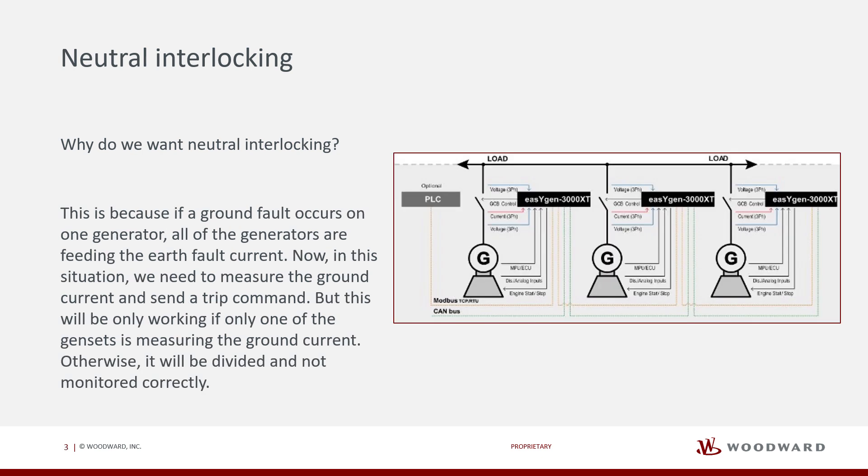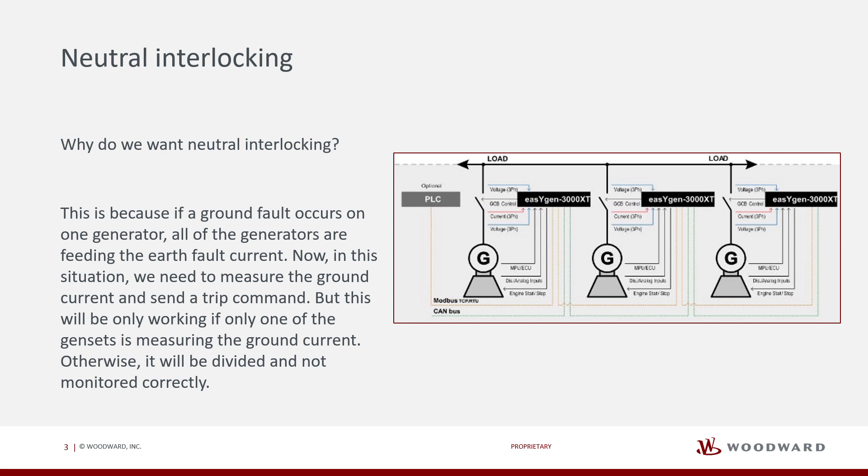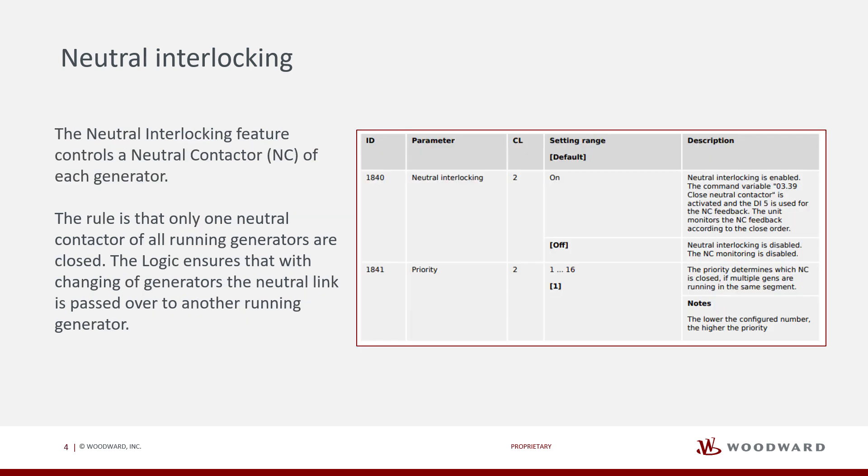This is because if a ground fault occurs on one generator, all of the generators are feeding the earth fault current. Now, in this situation, we need to measure the ground current and send a trip command. But this will only be working if only one of the gensets is measuring the ground current. Otherwise, it will be divided and not monitored correctly.